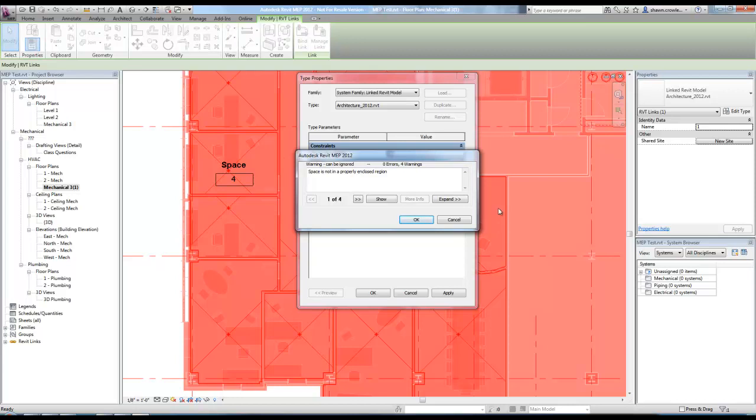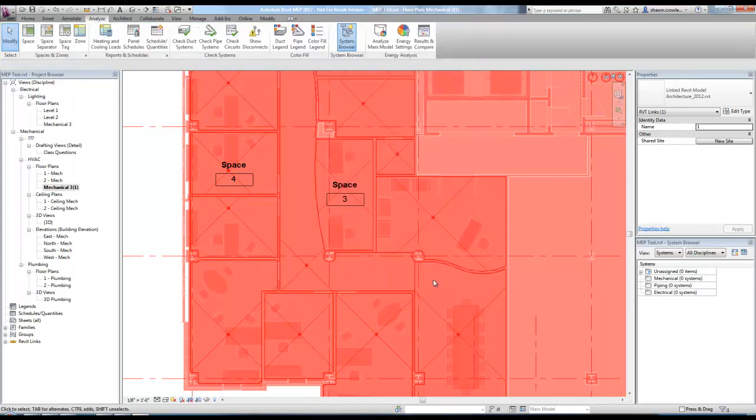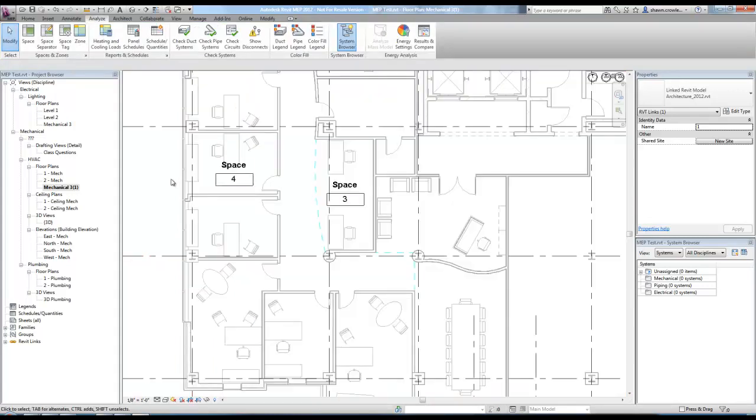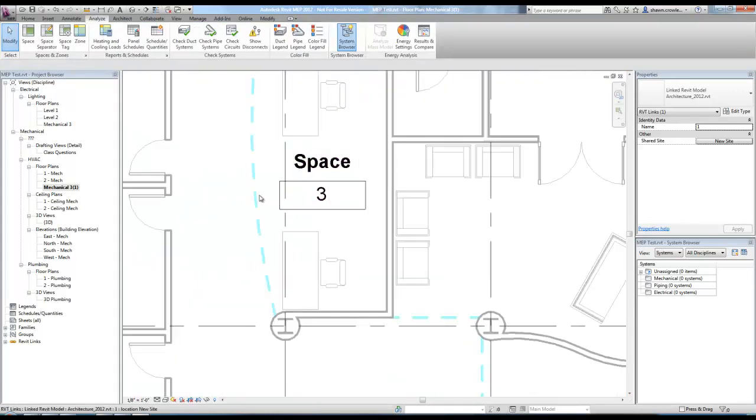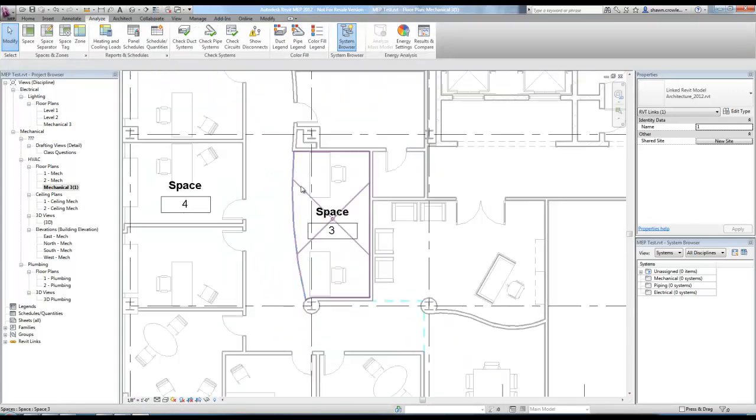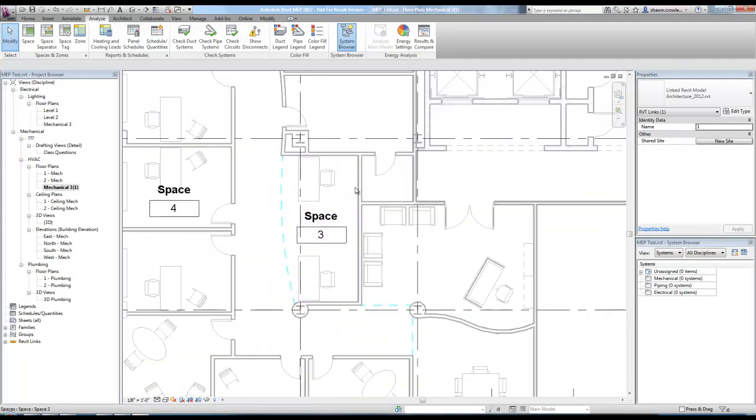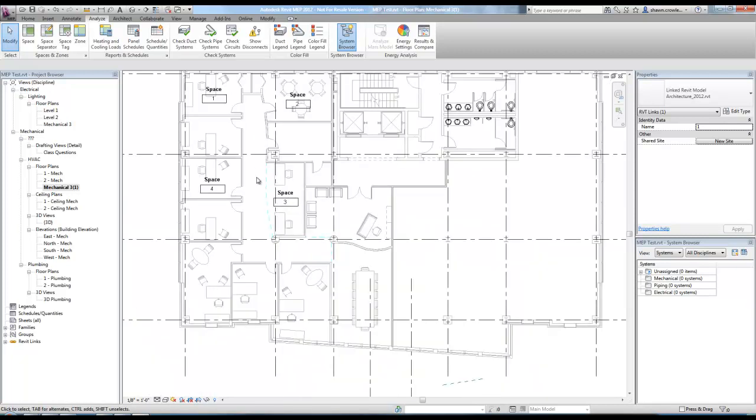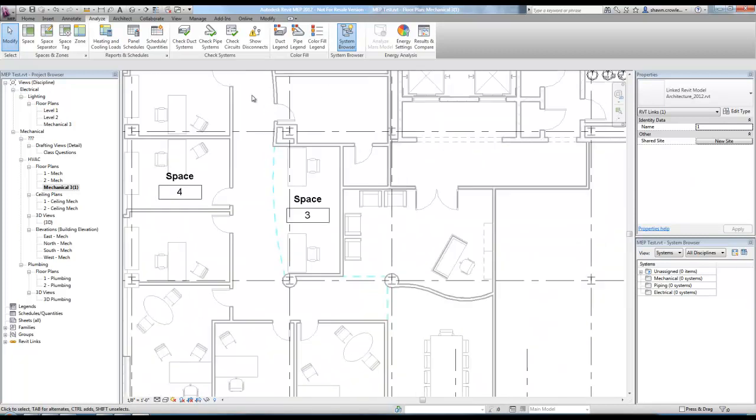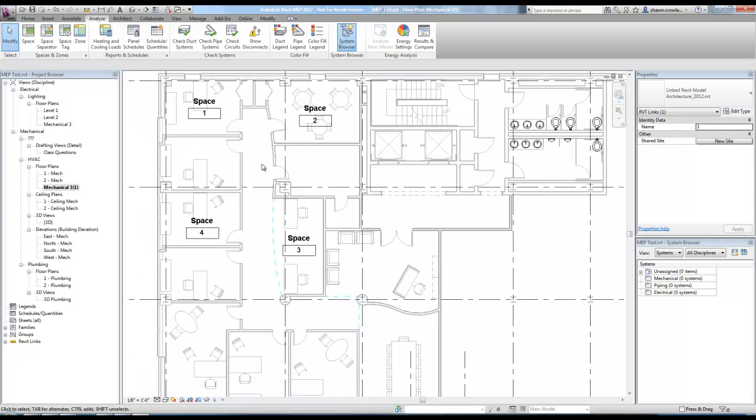So it's not too bad because what will happen is even if you try to turn off room bounding elements after creating those spaces, you're going to get an error that's basically going to say space is not in properly enclosed region. So the answer to it is more or less don't try to combine spaces that the architect hasn't. Otherwise, you're just going to get into a big mess. It's easier to just make sure those spaces have the same properties and assign them to the same zone.